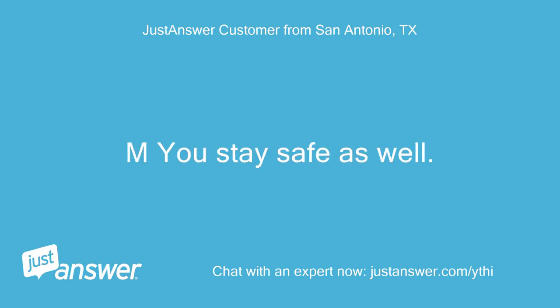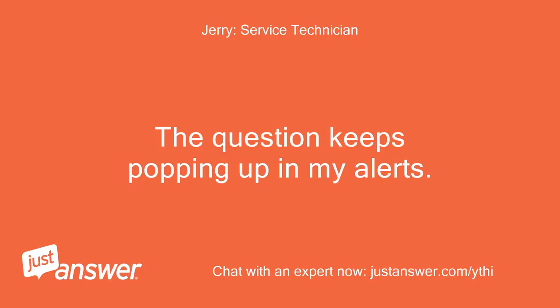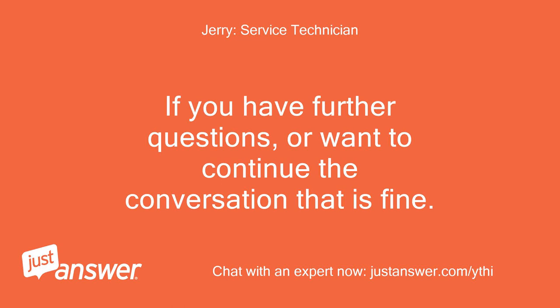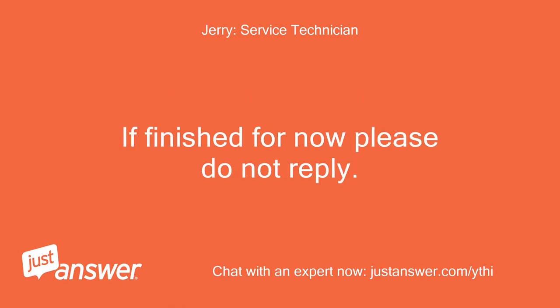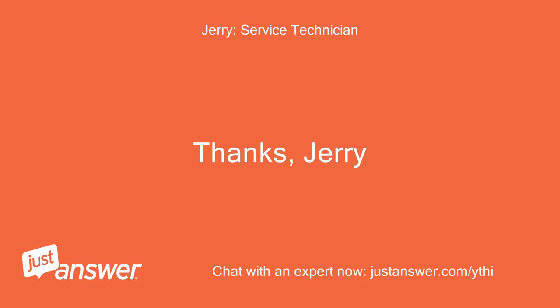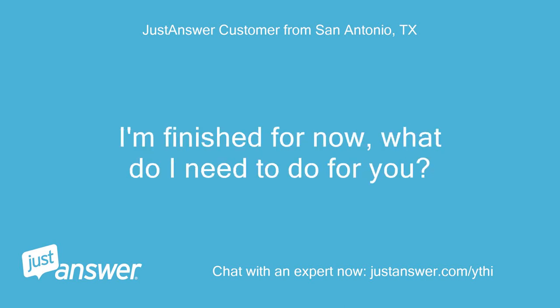You stay safe as well — thanks, Jerry. The question keeps popping up in my alerts; anytime you reply, it assumes I need to reply back until the answer is accepted. If you have further questions or want to continue the conversation, that is fine. If finished for now, please do not reply. I would appreciate a rating and accept so I get paid. Thanks, Jerry. I just changed the igniter, flame rod assembly, and the ignition transformer. The flame rod assembly was a little dirty and the tip is brittle, but doesn't look bad — I replaced it anyway and just powered back up. Time will tell.